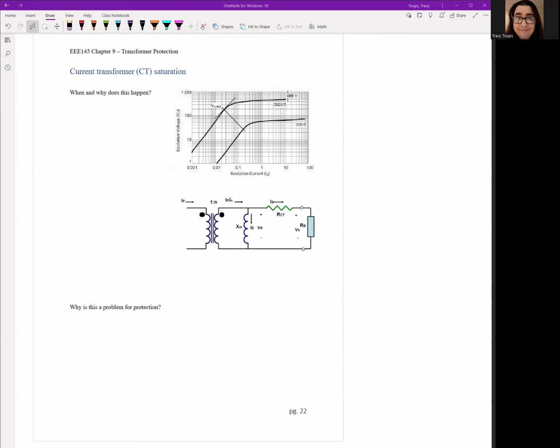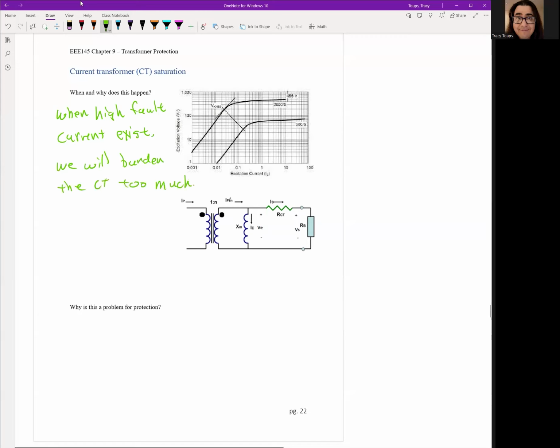The next thing that could cause problems for the 87 differential is when the CTs themselves get saturated. When and why does this happen? When high fault currents exist, basically when you have a pretty strong fault, we will burden the CT too much. It'll basically start breaking down, and this will cause the CT to become inaccurate.